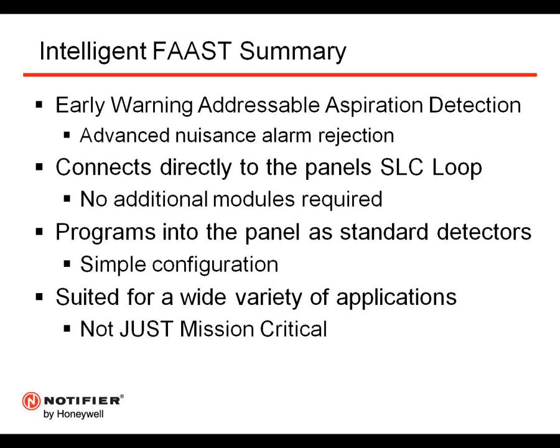Simple integration programs into the panel as a standard spot detector. So once they do the configuration with the Pipe IQ to set up the sensitivity of those thresholds, then it's just a matter of programming those five detector addresses into an ONYX series control panel using VeriFire tools. And as we went through the applications and the case studies, it's suited for a wide variety of applications, not just mission critical. So as you go out there and interface with your customers and engineers, just think about some of the different applications in which Intelligent FAAST can be applied.